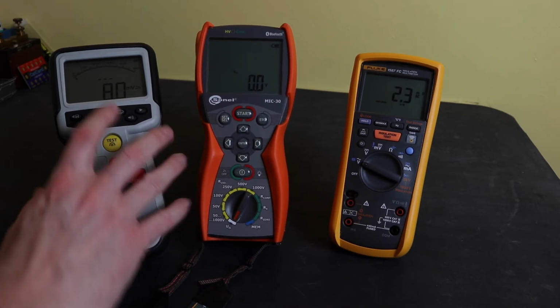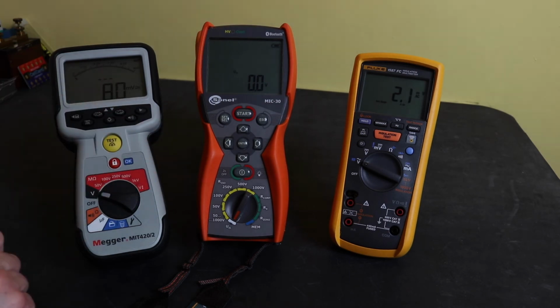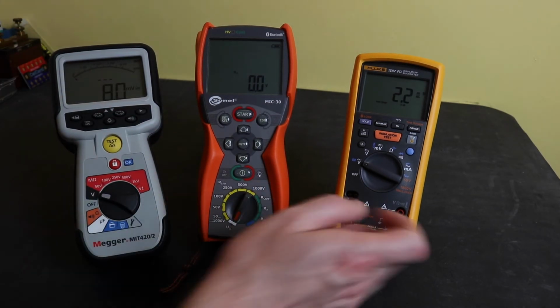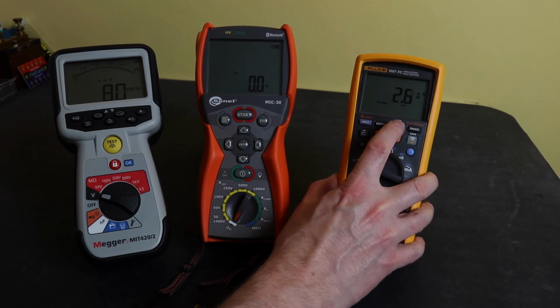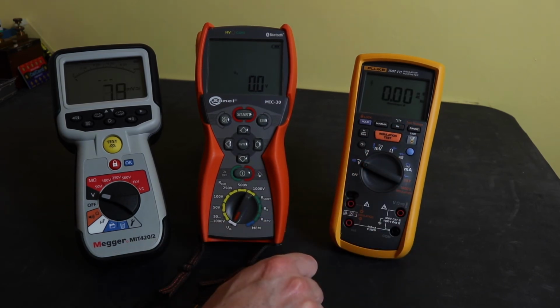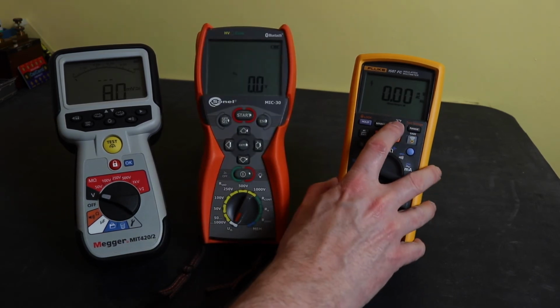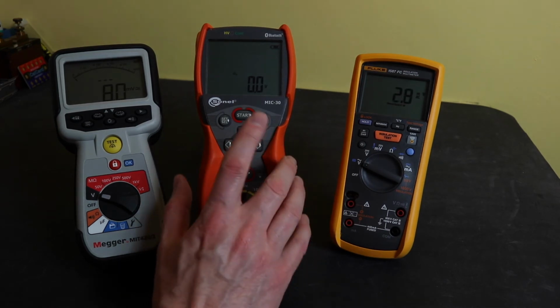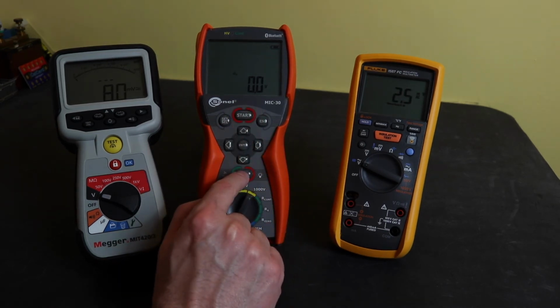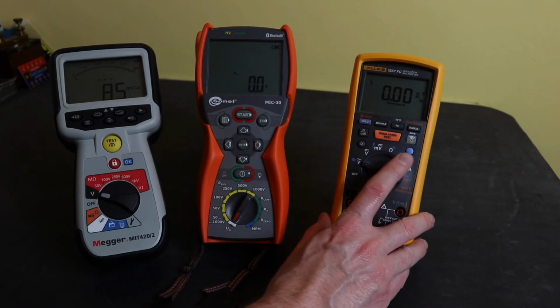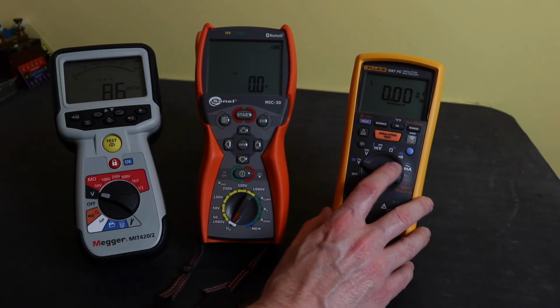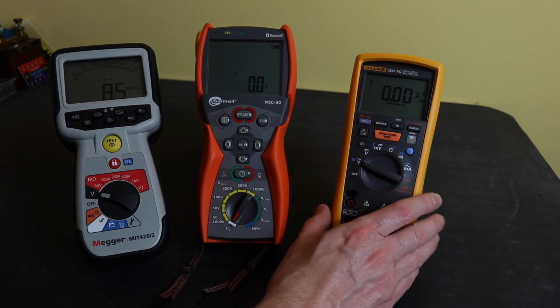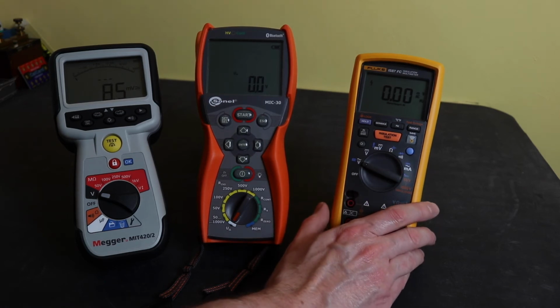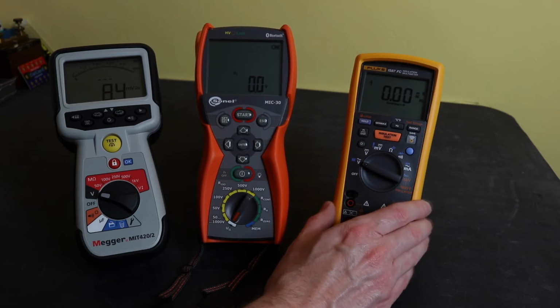Frequency when you're on AC mode will be displayed in the top of the screen here. For Fluke, you have to hit the Hertz button and you can get the Hertz displayed. And for the Sonel here, you don't get any Hertz measurement capability whatsoever. On the Fluke here, it will go from 0.01 Hertz up to 99.99 kilohertz, so a much wider range for frequency measurement on this instrument.